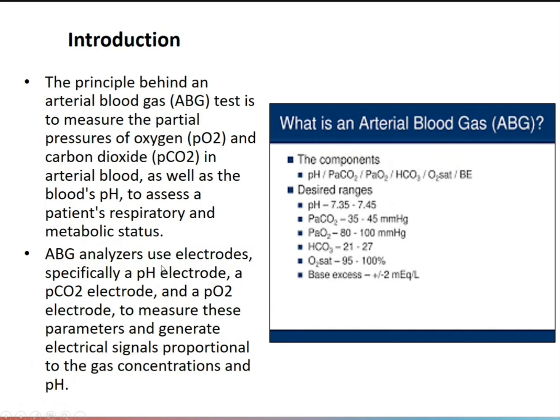They are direct. That is one difference when you compare the electrolyte values of your autoanalyzer and the ABG machine. The ABG machine uses direct ISEs, whereas the autoanalyzers have indirect ISEs. That means there is a dilution which takes place in indirect ISEs. So from an accuracy point of view, direct electrodes are much better and more accurate as compared to indirect ISEs.